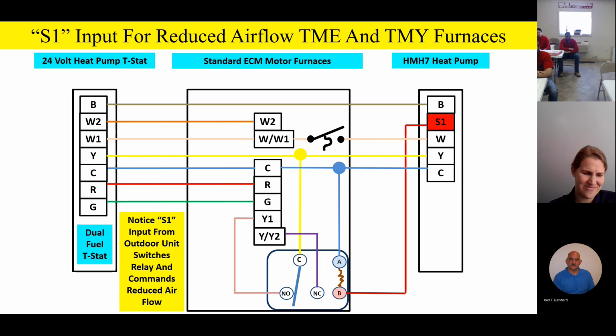It's just that these kits that we put together for you, the 001 and the 002 kit, are a handy little kit that has the biflow filter dryer already in there. It's got some pre-made wiring harness for you, so you don't have to make up a wiring harness or make up low voltage wires. And then it's got the little relay kits. So, it's up to you guys, but don't think that you have to use that kit. If you've got your own biflow filter dryer on your truck and you've got some peanut relays, you can make up your own kit if you want to. It's no big deal. Just for convenience, we offer those kits. Any questions on that? Okay, so you guys can see, like I said, this is basically just a little peanut relay inside the unit for switching that airflow. Real simple.